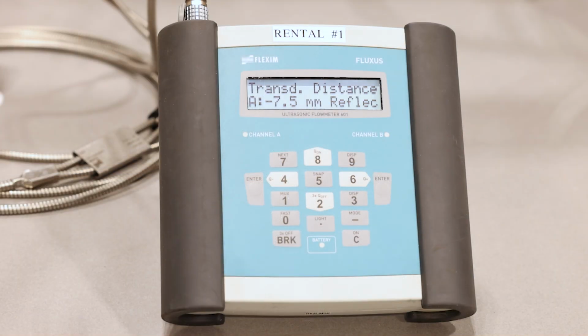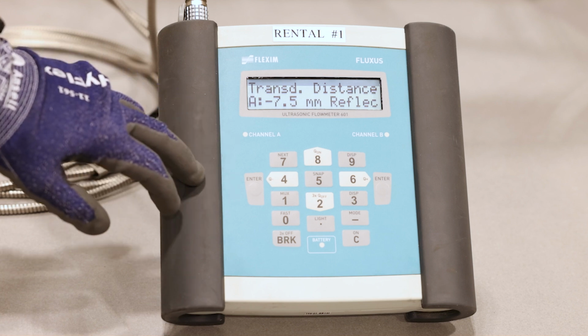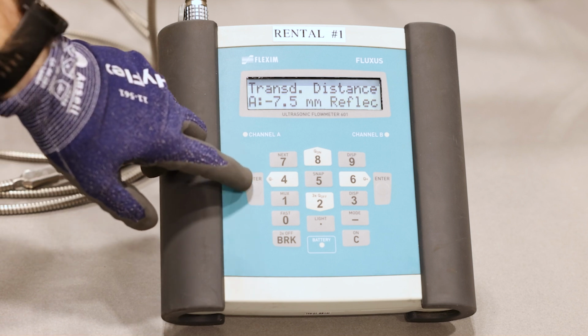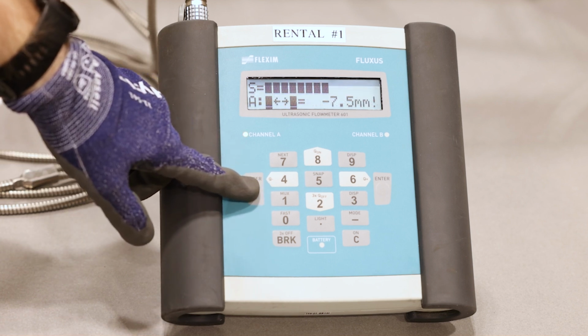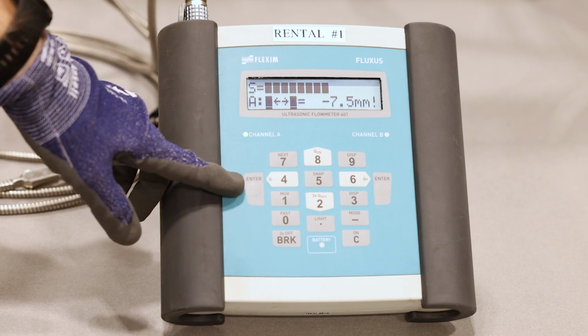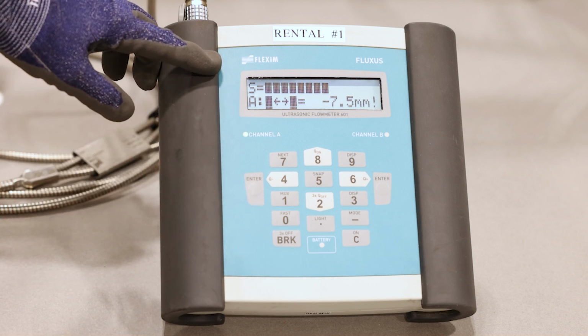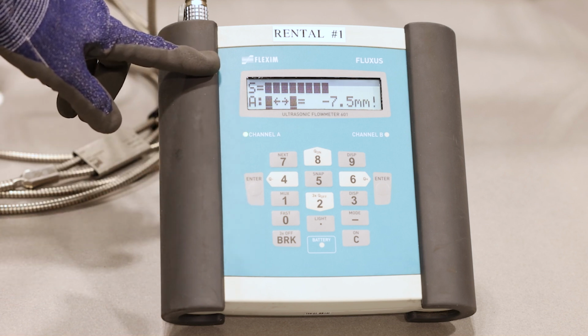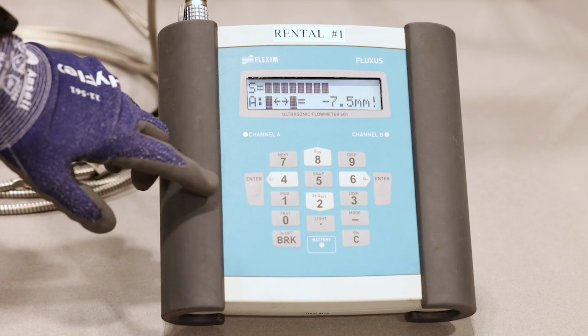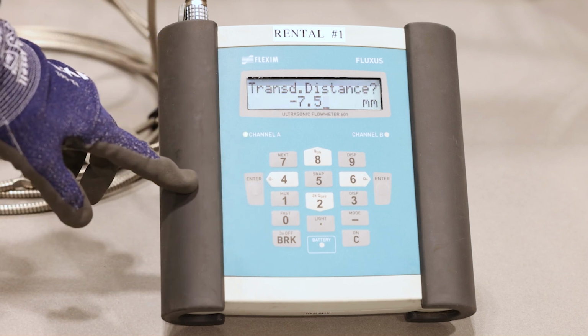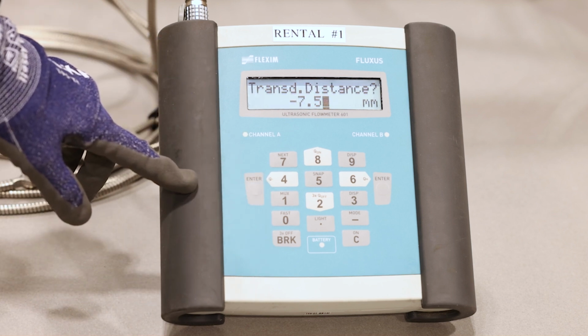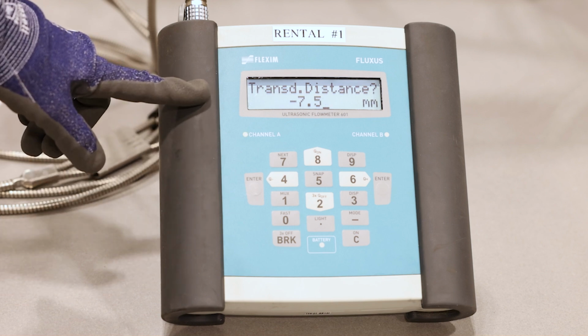Back in the measuring screen, we can enter past the transducer distance screen. This screen shows us our signal amplitude, and we should typically have at least 3 bars, which is approximately 30% of signal. This next screen is asking for the actual distance that we installed the transducers at. Remeasure the distance to give an exact reading.